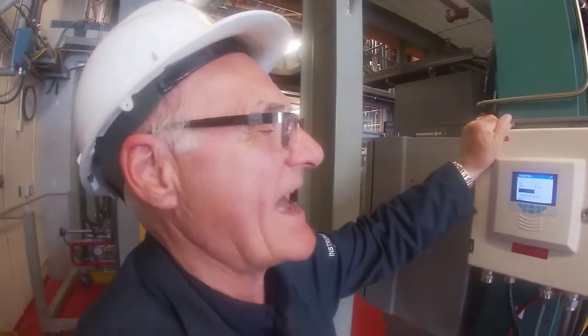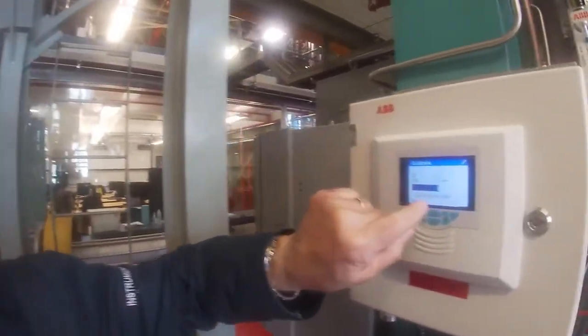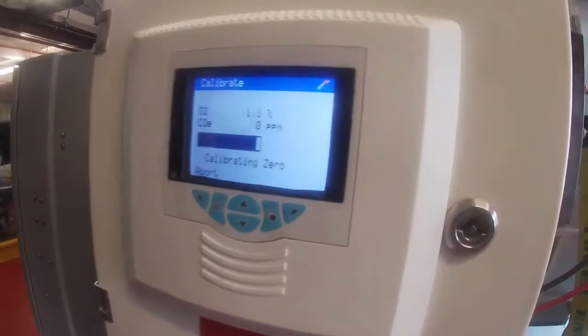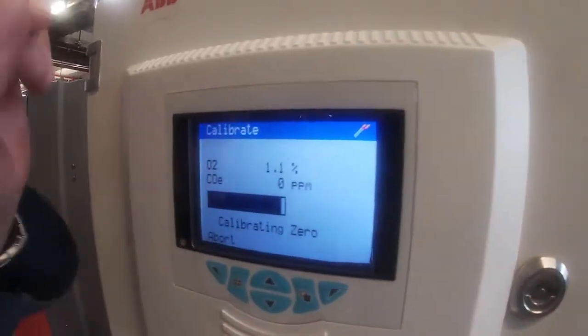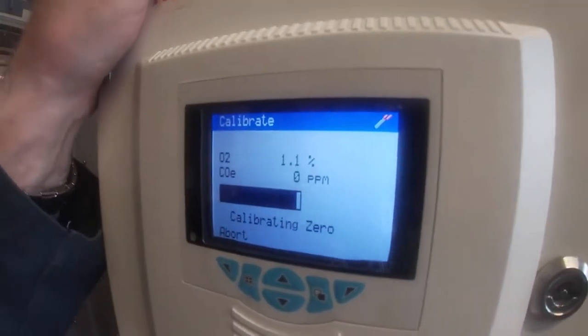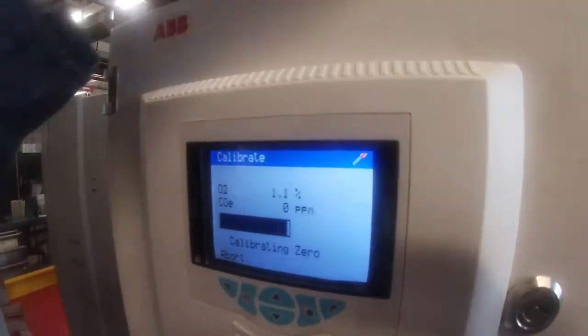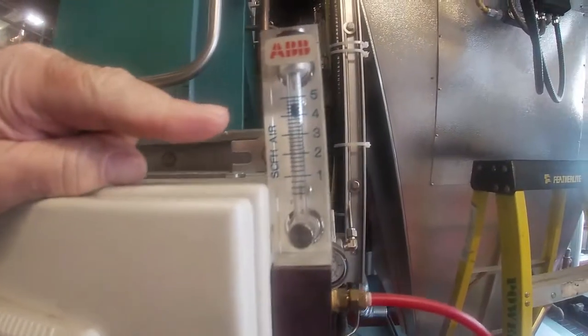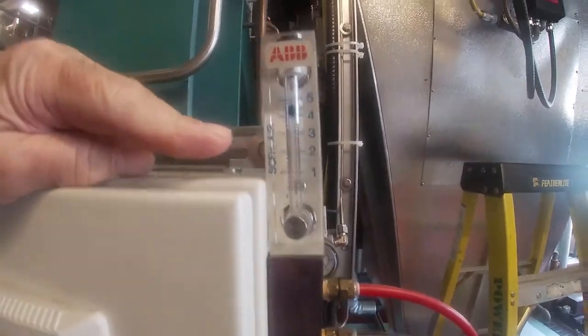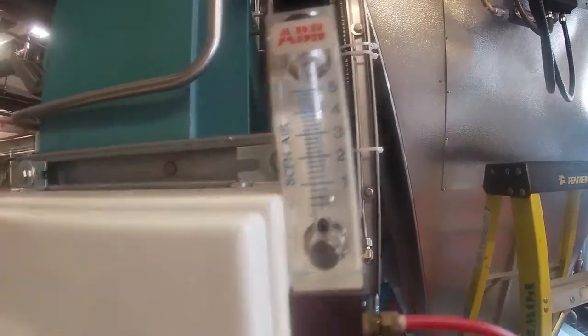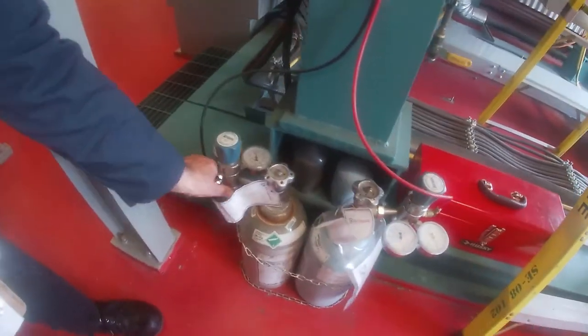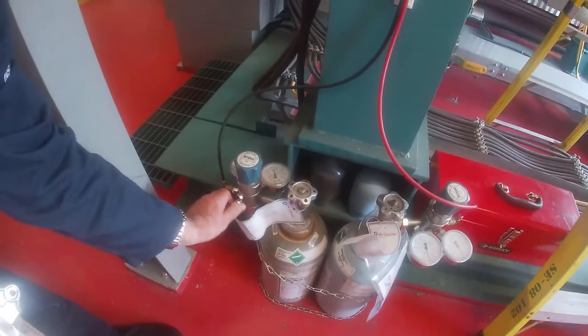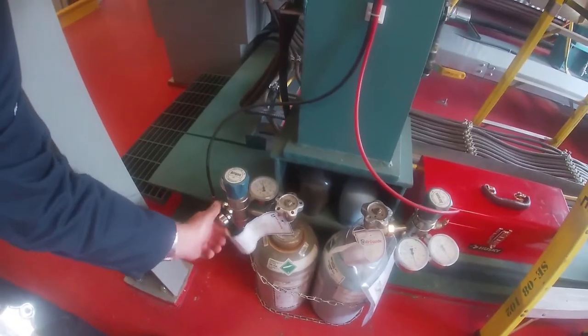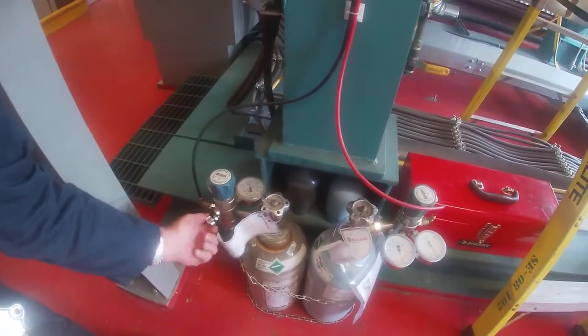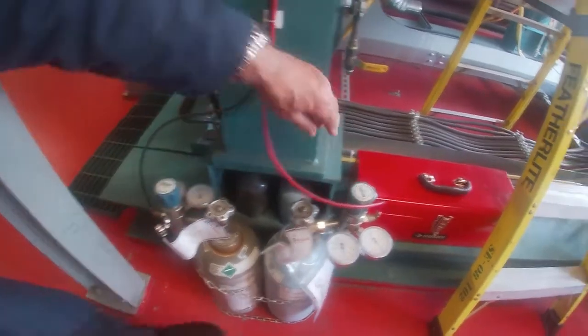Okay, in about the last 30 seconds, it actually takes the values that it saw, and you can see it's pretty close. It's down at 0 ppm already, and it's at 0.1. In a few seconds, you'll see this guy drop. Okay, it's shut off the 0 gas. Down here, I manually shut off the span gas. I'm going to turn it back on again, and I'm going to turn the 0 gas off.